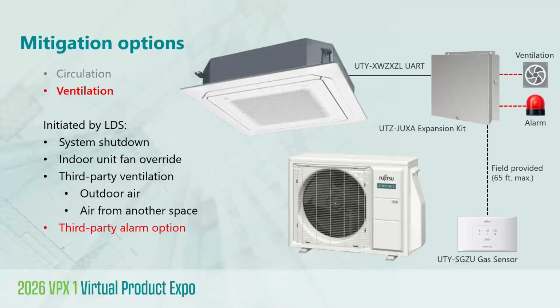So in other words, the expansion kit can be used strictly for circulation. It can be used just for ventilation, or it can be used for circulation and ventilation, or it can be used for circulation, ventilation, and alarm. So again, you can mix and match, you might say. Now, when it comes to inputs, the expansion kit offers a lot of inputs, if I could just summarize simply by saying they are identical to the traditional external inputs that we've used also for years, that you're probably familiar with, such as Operation Stop, Emergency Stop, or Force Stop. Now, those kinds of external inputs could be used for auxiliary devices such as a window sensor, occupancy sensor, condensate switch, or even, say, a smoke detector.